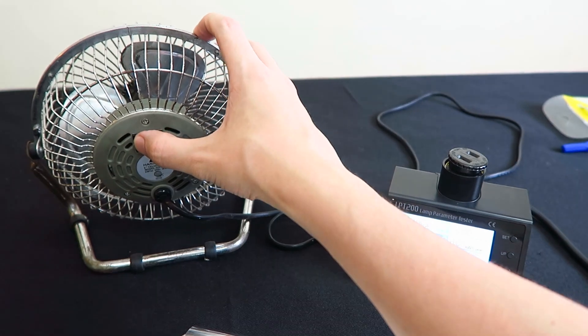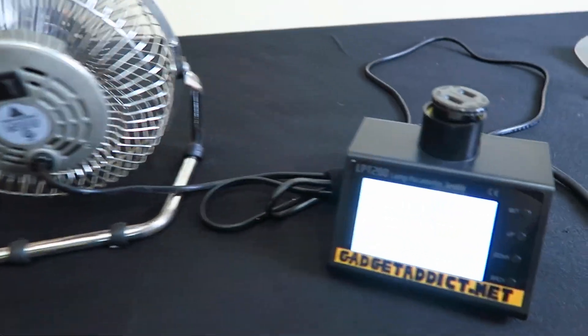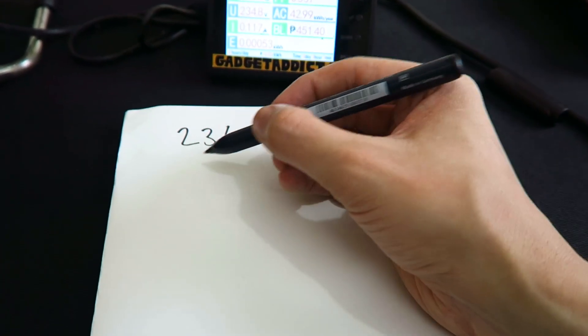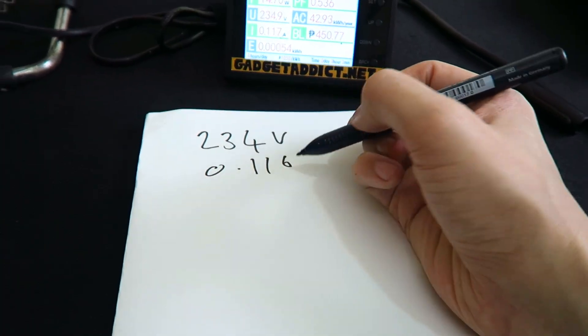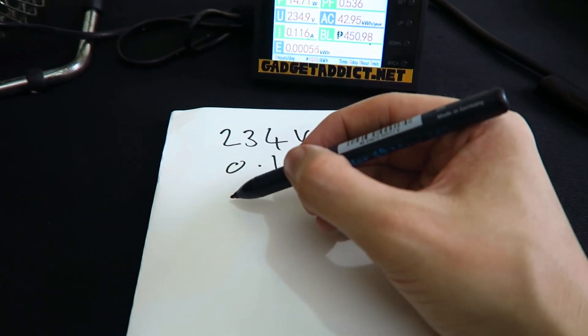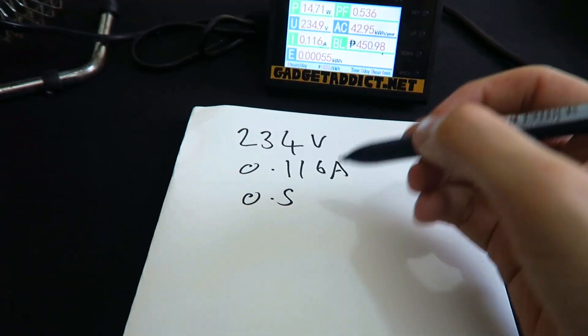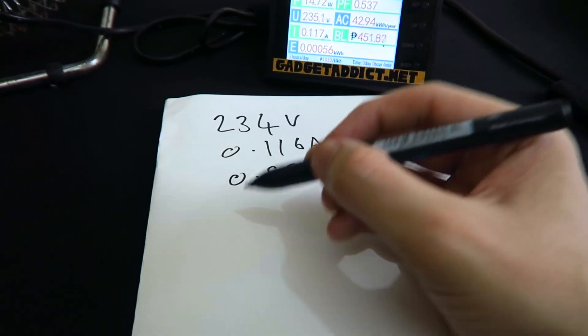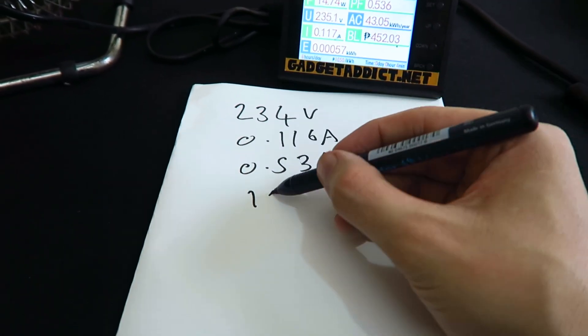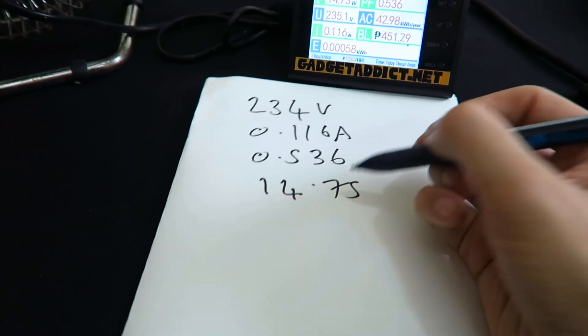Let's put the fan on its top speed and then look at the power meter. Let me write those numbers down. So we've got 234 volts, 0.116 amps, power factor of 0.536, and our wattage around 14.75 watts.